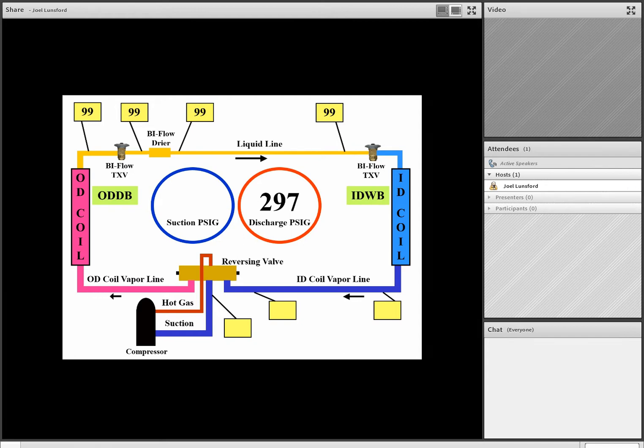So as we take a look at subcooling, our step number 1, we're going to take 297 pounds of pressure, and this is an R22 call, so at 297 pounds of pressure, we have a pressure temperature conversion of 130 degrees. Step number 2, we see that we have a 99 degree liquid line temperature leaving the warm coil. So the difference between 130 and 99 is about 31 degrees. Now remember, team, in the cooling mode of operation, we're looking for about 10 to 15 degrees of subcooling in the cooling mode of operation, which we're in.